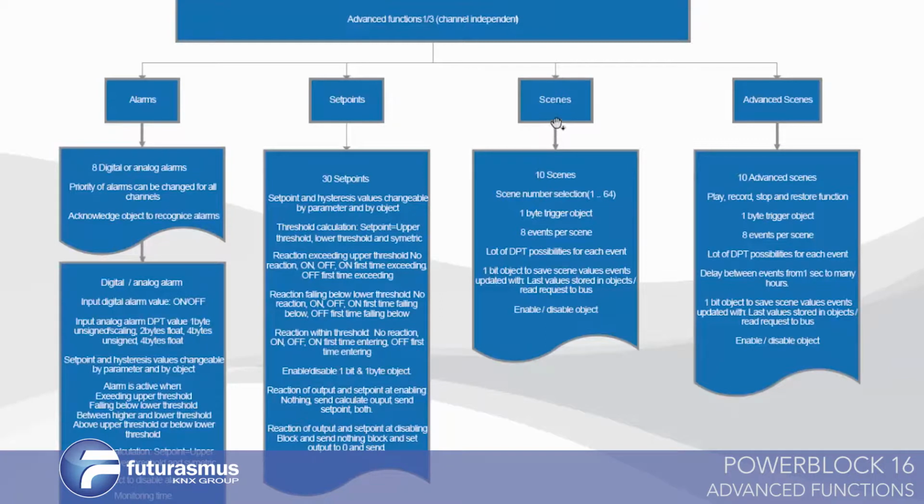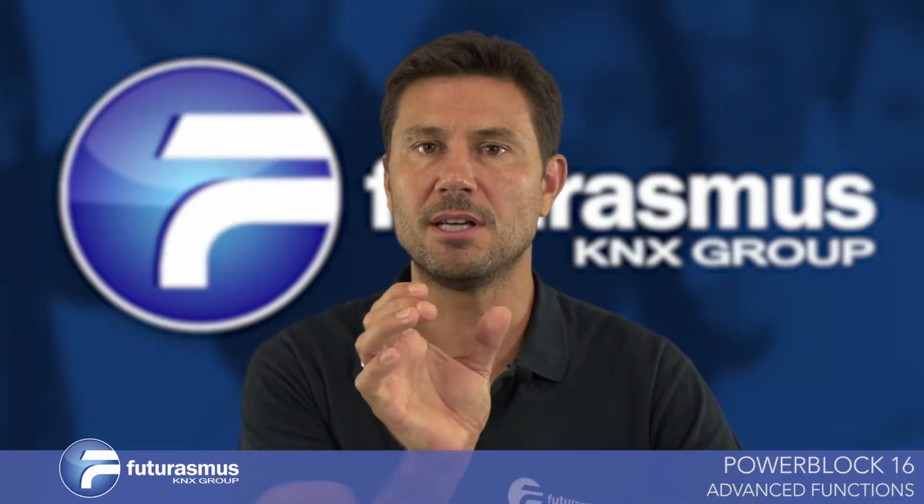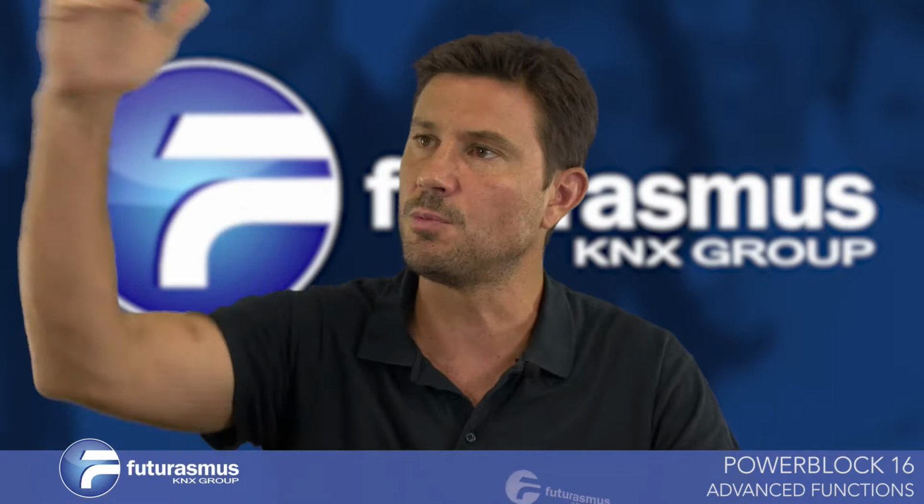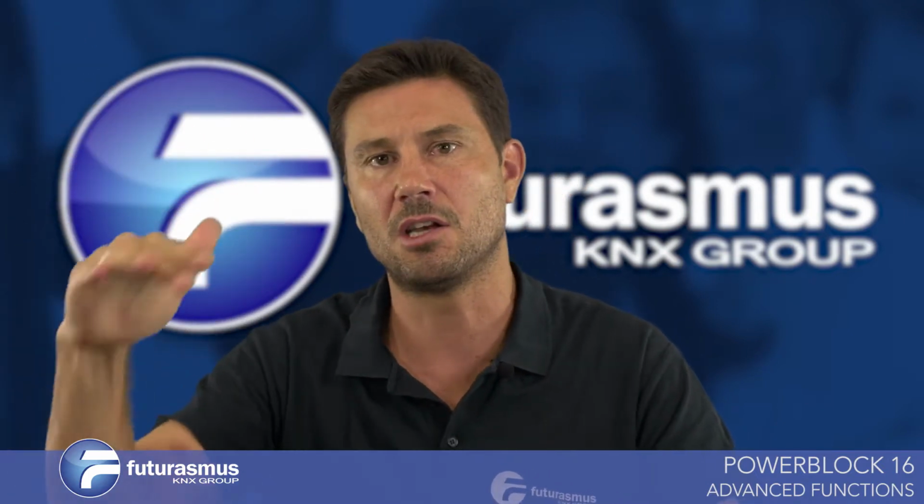Then the scenes, there are 2 types of scenes: the normal scenes and the advanced scenes. These are scene modules with its input object and output objects, which can then be linked to different actuators which don't have a scene function, or to different devices which don't have the scene object. So these output objects can be set to any of the normal data point types, so that you can send, for instance, this one on, this one off, this one to 80%, and so on.